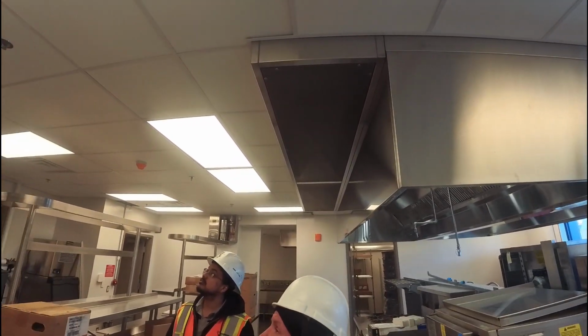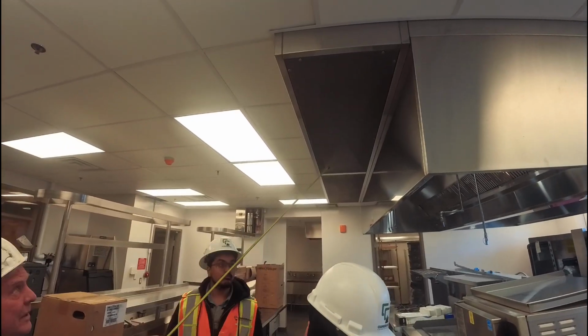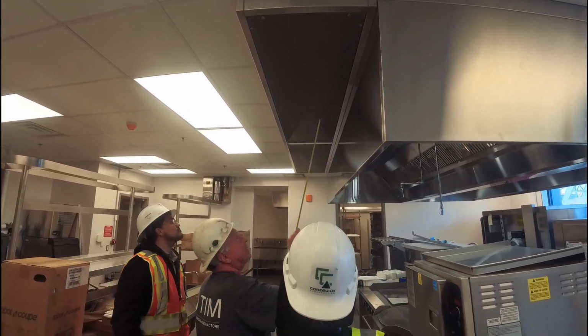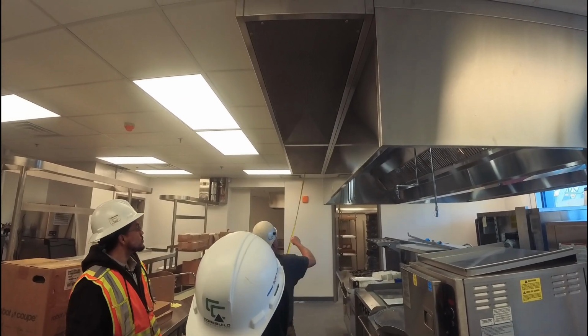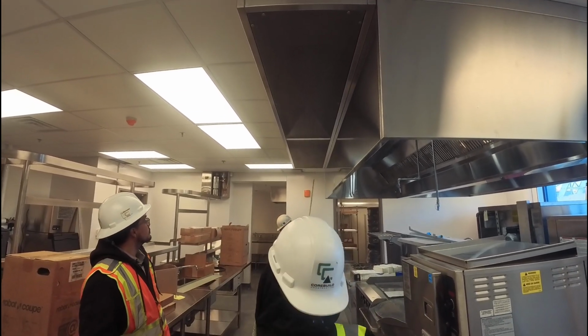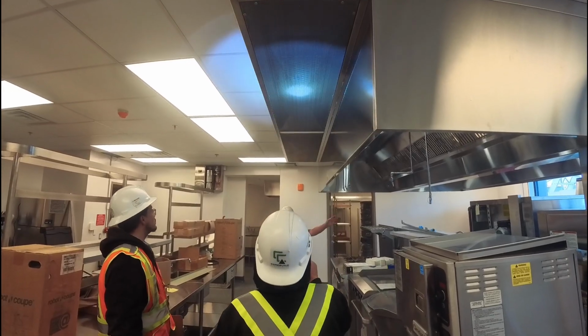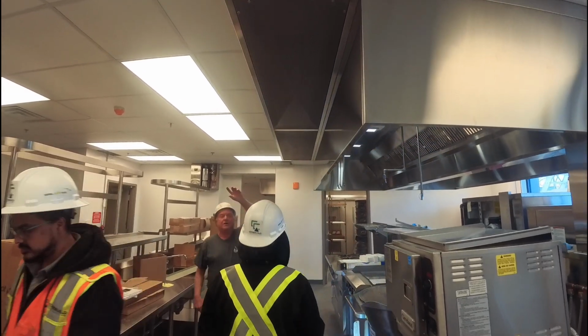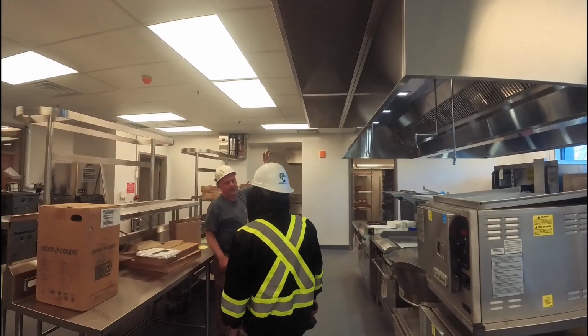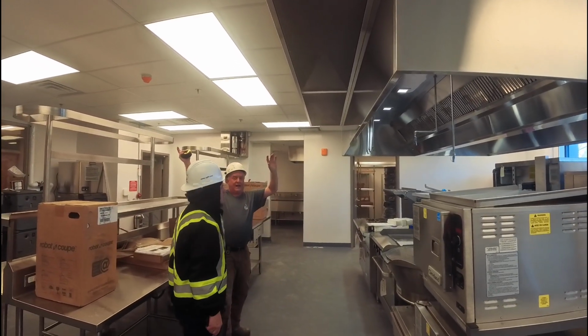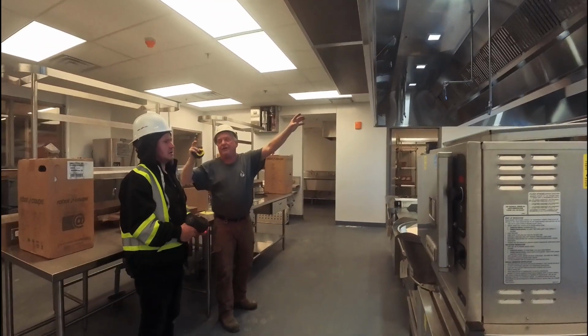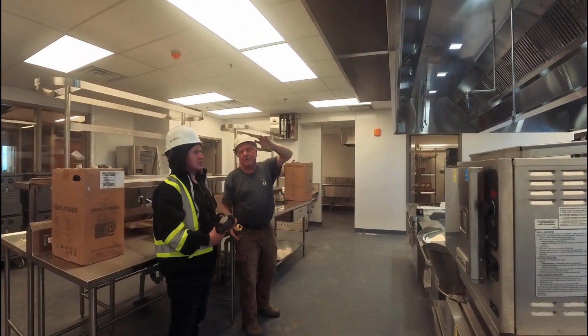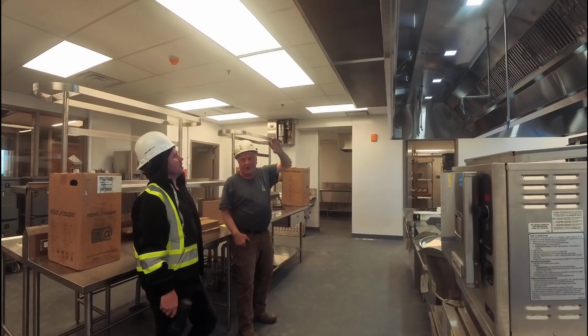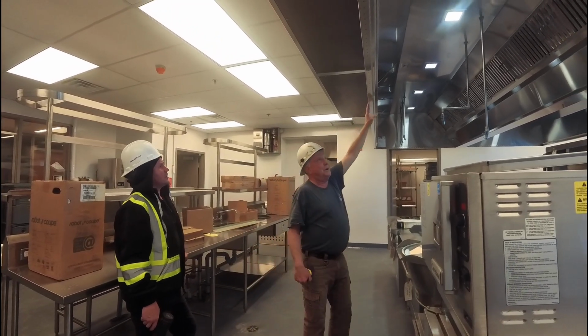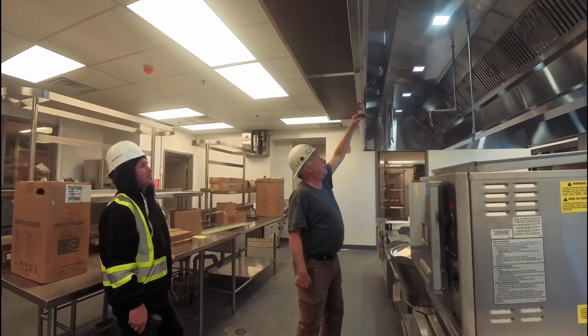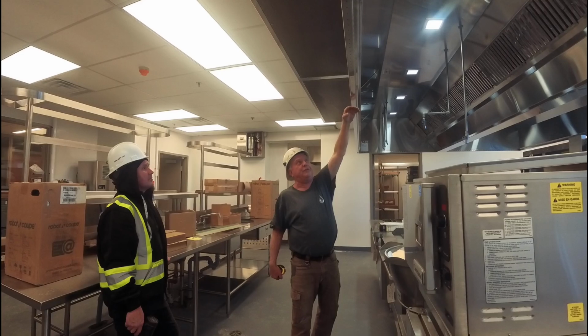And the first takeoff goes across this way, and it picks up this guy here. This is where your makeup air is coming out. It's a great big diffuser, big opening. There's your second one right there. On the other side of the hood, there's 2 more. Each one of these runs of duct also has a duct heater associated with it. You're pulling 40 below air out of that unit up there on the roof. You don't want to feed that right in here. So that's why they put a duct heater on each one of these runs to bring it down to doable air. And this thing is running right now. You feel your hands on that.